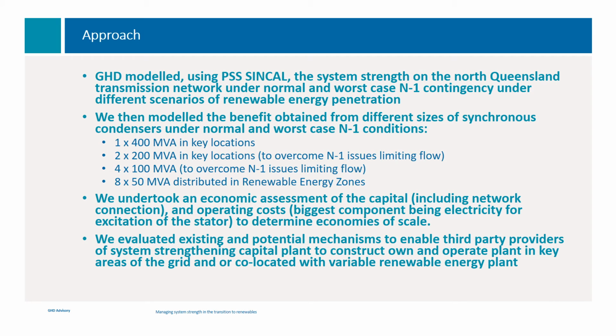In undertaking the study, we modelled, using PSS SINCAL, the system strength on the North Queensland transmission network under normal and worst case N-1 contingency and under different scenarios of renewable energy penetration. We chose a size of synchronous condenser of 400 MVA as being a typical size that you might place in a centralised location to provide cover, system strength cover that is, over a broad area.